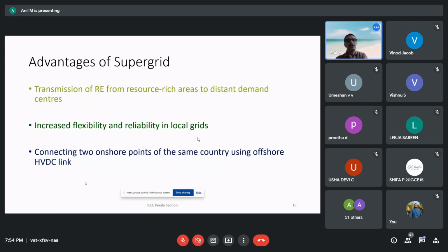Advantages of super grids: transmission of renewable energy from resource-rich areas to distant demand centers can be achieved using super grids, increasing flexibility. Reliability in local grids can also be increased with greater interconnection. Another advantage is connecting two onshore points of the same country using an offshore HVDC link, since the NIMBY, or not-in-my-backyard, syndrome creates problems in drawing transmission infrastructure through land. Using a submarine cable to connect two onshore points within the same country allows the HVDC link to function as a bulk power interconnector, which is a major advantage of super grids.